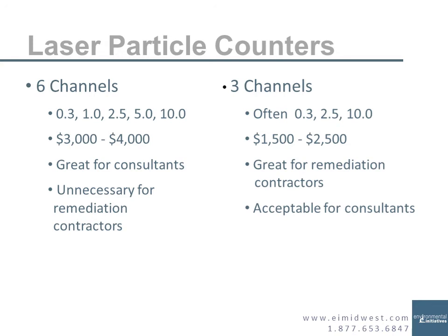So some HEPA equipment is actually very bad at removing particles that are bigger than 5 micron or 10 micron. They'll be 40% efficient, 60% efficient, but yet they'll be 99.97% efficient at 0.3 because that's what they're being tested at. So what's nice about a laser particle counter is that you get to see the range of particle sizes and how that equipment is doing.